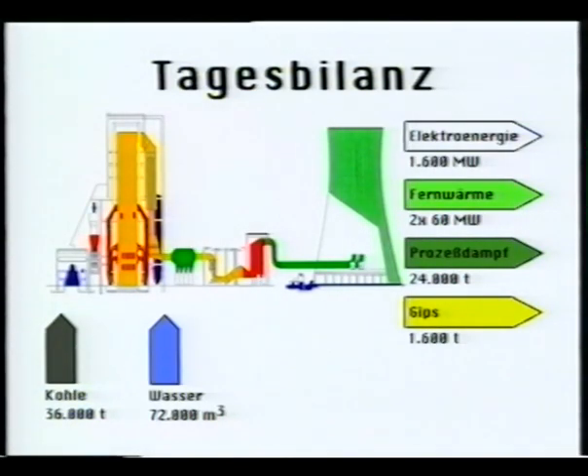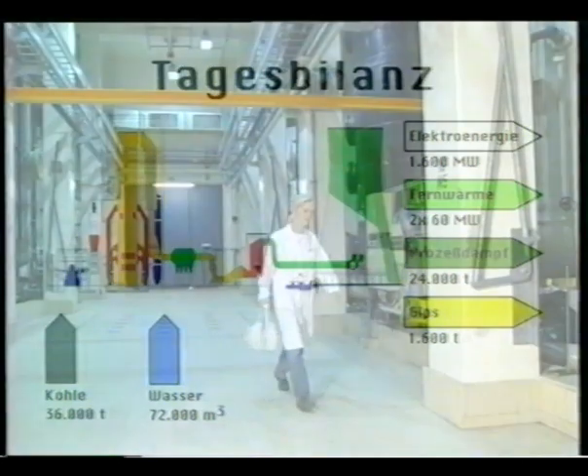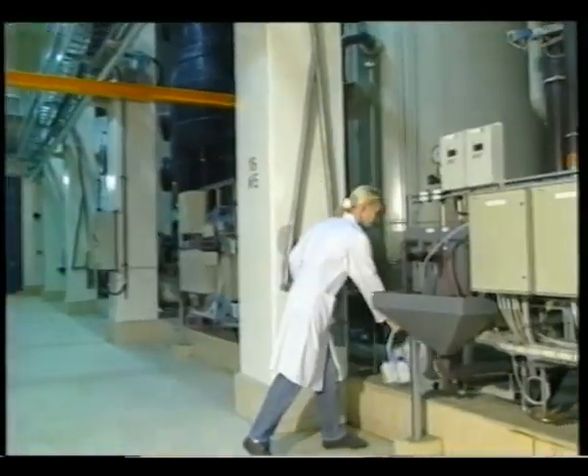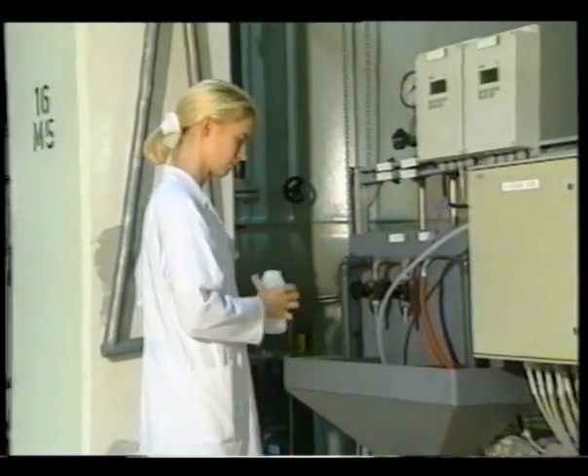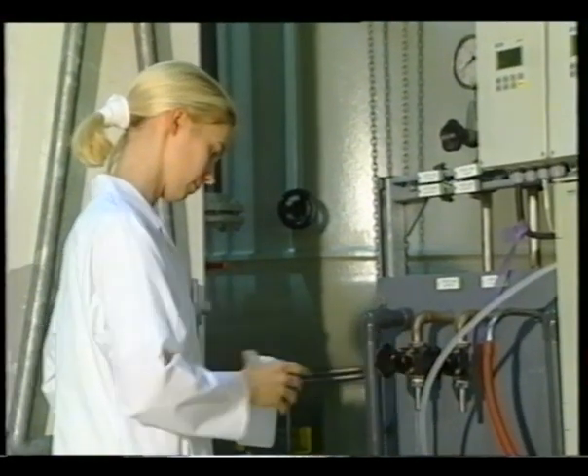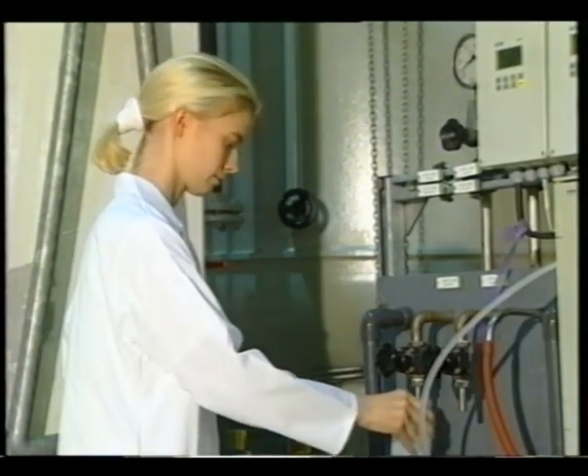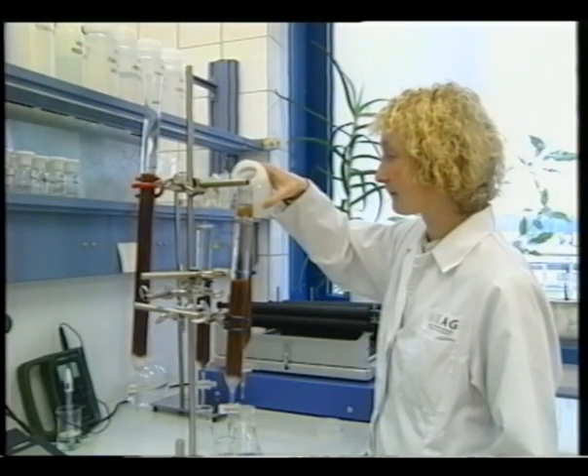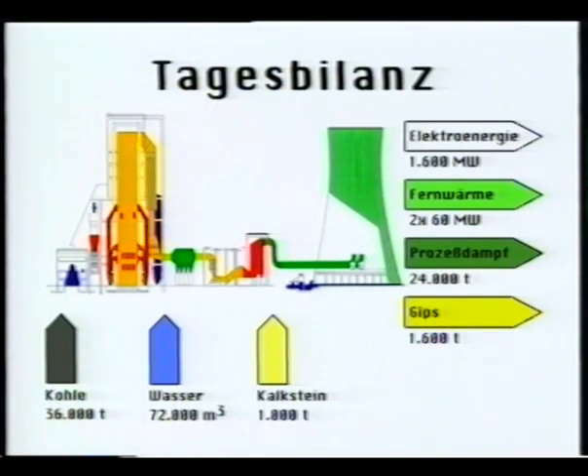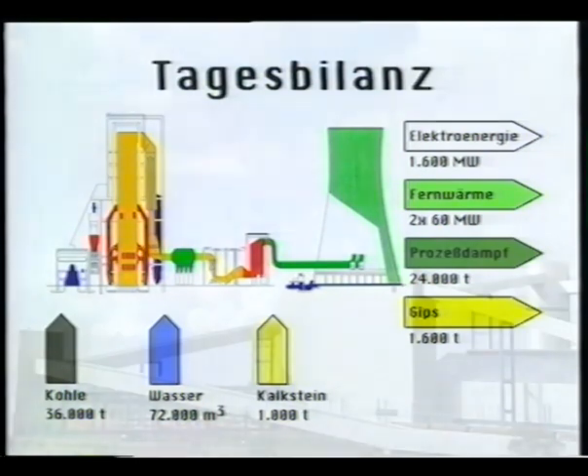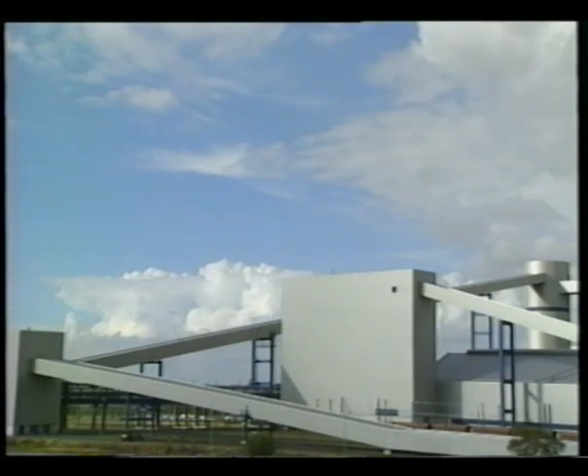Water. About 70,000 cubic meters of water have to be prepared before being used in the power plant process. The water is pumped from the groundwater of the open cast mine. Limestone. The flue gas desulfurization needs about 1,000 tons per day.